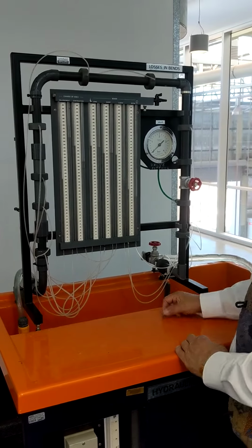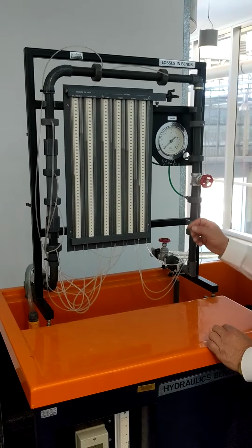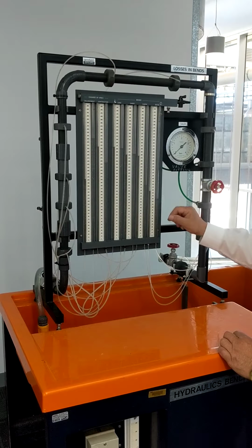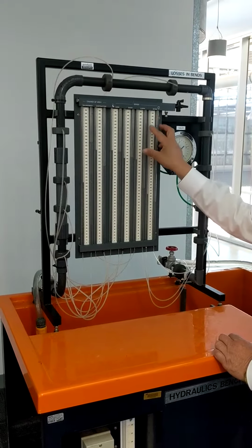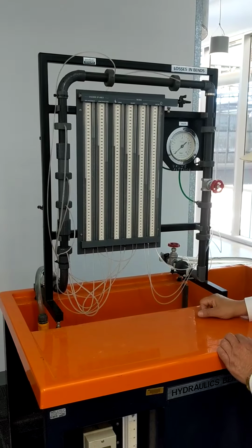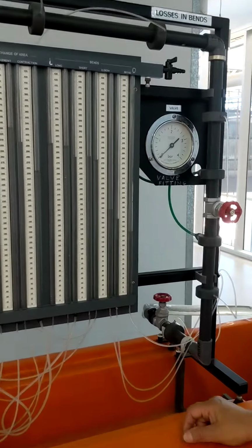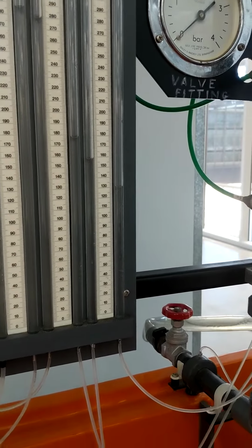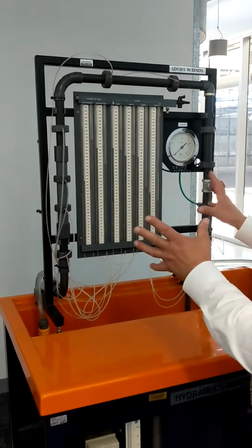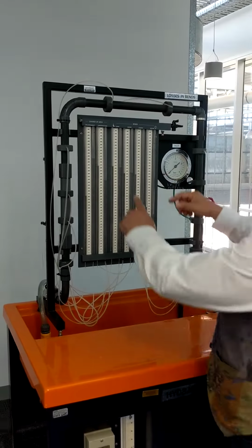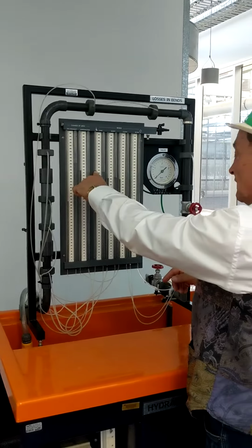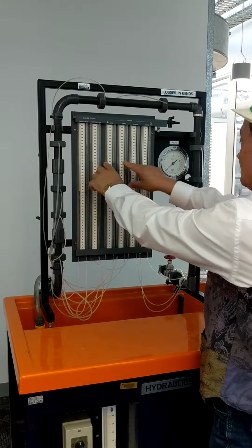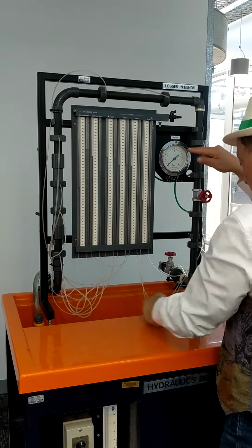And the practical suggests the different flow rates to be determined by a difference of 80, 160, 240 and 400 across the mitre. At the moment we've got approximately 65 or so, but that once again is not critical because it is just to determine a variety of data points. So in this case we would measure the difference between the inlet and the outlet and take away that value from this value, and that will be the head loss through the whole system.